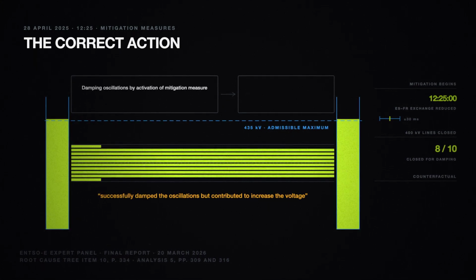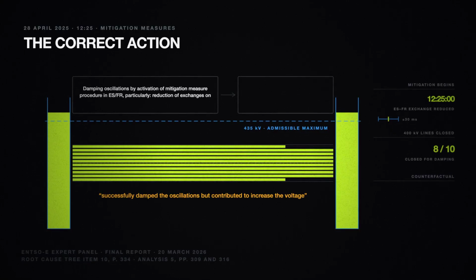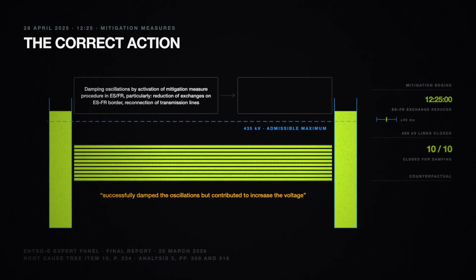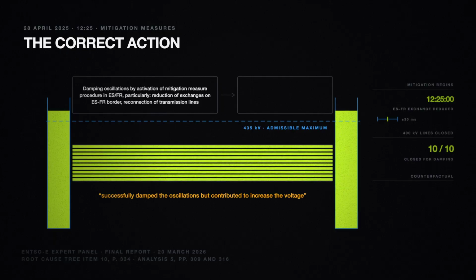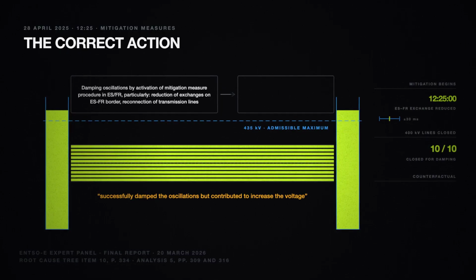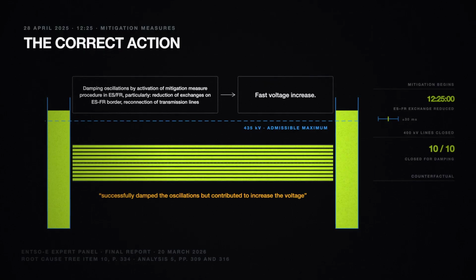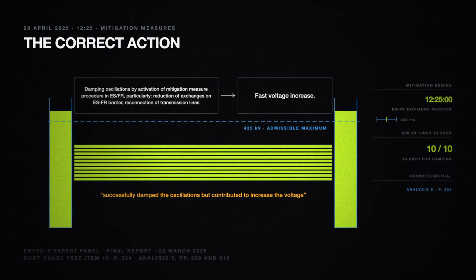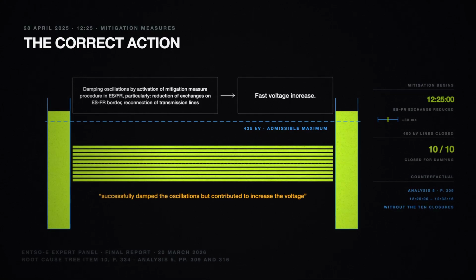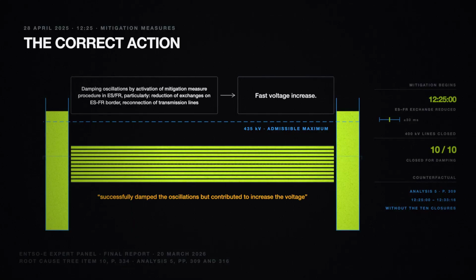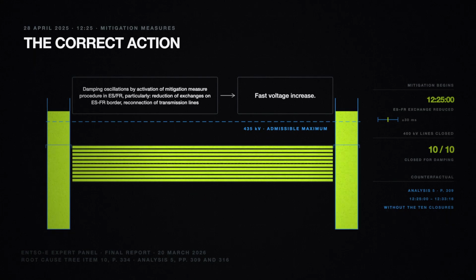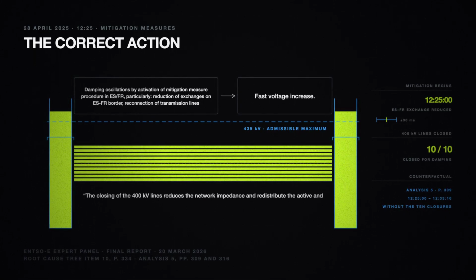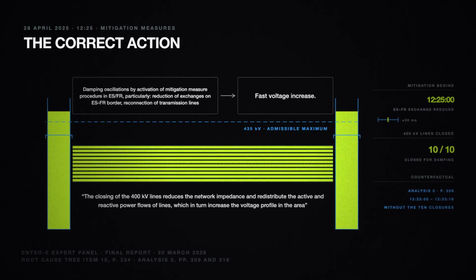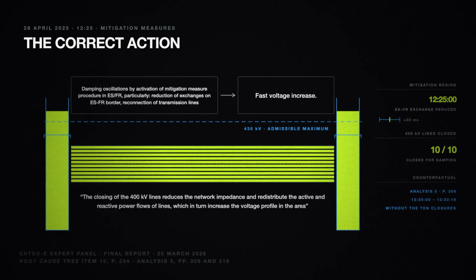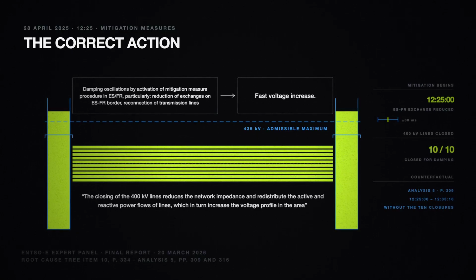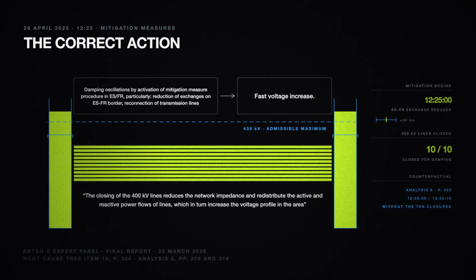There is a box in that tree that reads, damping oscillations by activation of mitigation measure procedure, reduction of exchanges on the Spanish to French border, reconnection of transmission lines. It feeds directly into a box that reads, fast voltage increase. Analysis 5 reruns the period from 1225 to 1233 and 16 seconds, without the 10 400 kilovolt lines that were closed for damping. Its finding, in its own words, the closing of the 400 kilovolt lines reduces the network impedance and redistributes the active and reactive power flows of lines, which in turn increase the voltage profile in the area.